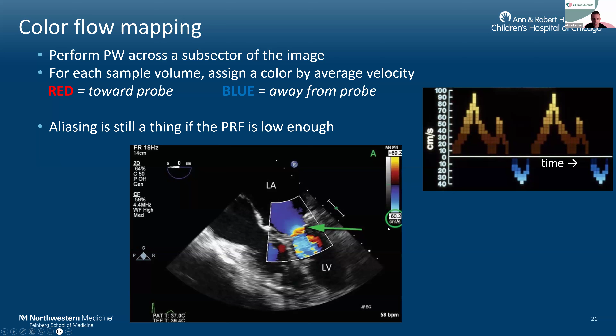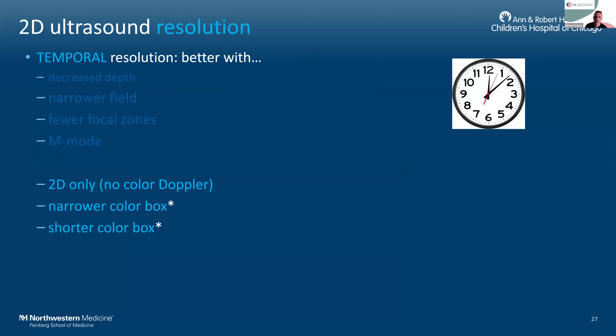So finally, when we add color mapping to our image, our temporal resolution is also affected by the size of the color box. So our frame rate will be affected by how narrow the color box is. Narrower is a better frame rate. A shorter color box also gives you a better frame rate. But of course, sometimes we need to trade off frame rate if we need to fully investigate blood flow of interest.